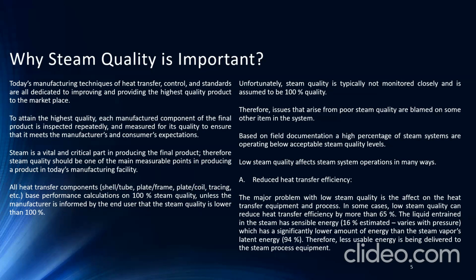So the liquid entrained in the steam has sensible energy, 16% estimated, which varies with pressure, which has a significantly lower amount of energy than the steam vapor's latent heat, 94%. Therefore, less usable energy is being delivered to steam process equipment. And check that when you design.